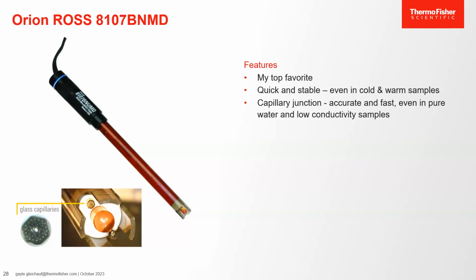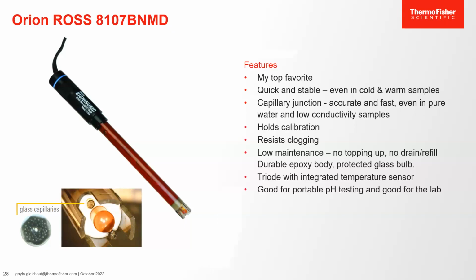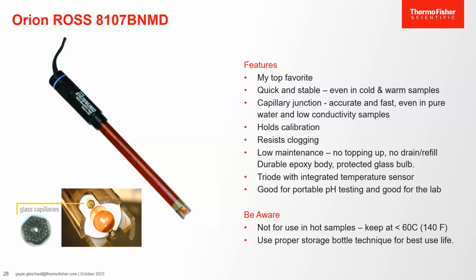This is my favorite pH electrode. It has a unique glass capillary junction and a Ross gel reference, which makes it a top performer. It's accurate and fast, even in pure water and low conductivity samples. The calibration holds well, and the capillary junction resists clogging. It is a low maintenance electrode. It has a durable epoxy body and a protected glass bulb. It's a triode with an integrated temperature sensor, and it's good for portable pH testing and in the lab. Be aware it's not for use in hot samples. Keep it at less than 60 degrees C or 140 degrees Fahrenheit. Use proper storage bottle technique. We'll talk about that shortly.